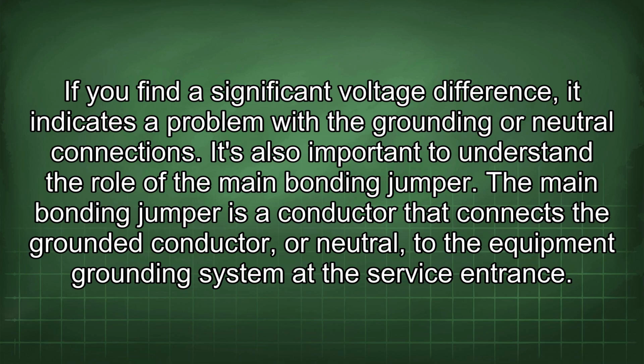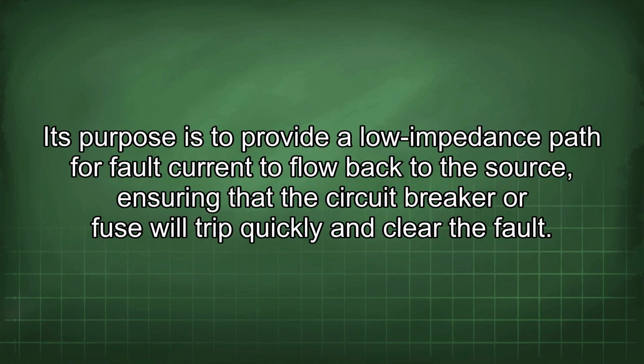It's also important to understand the role of the main bonding jumper. The main bonding jumper is a conductor that connects the grounded conductor, or neutral, to the equipment grounding system at the service entrance. Its purpose is to provide a low impedance path for fault current to flow back to the source, ensuring that the circuit breaker or fuse will trip quickly and clear the fault.